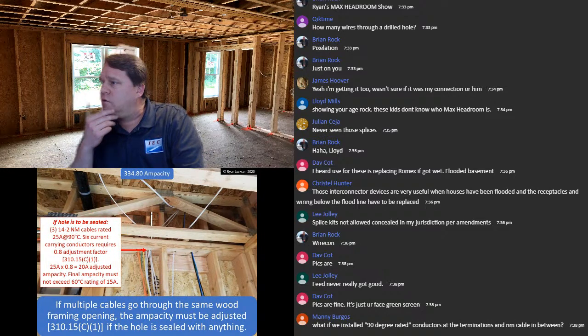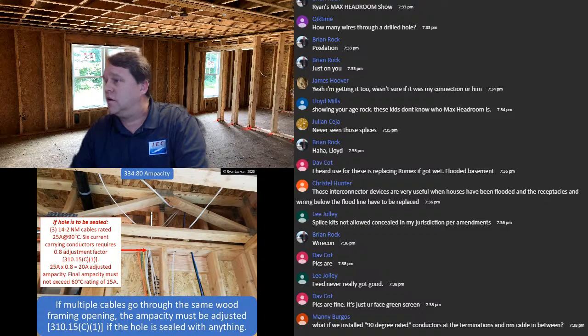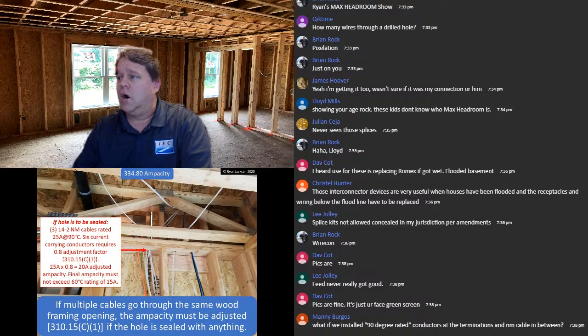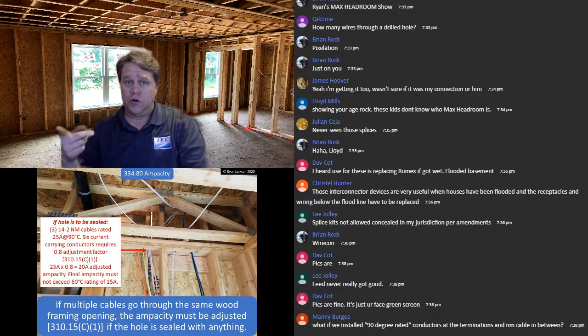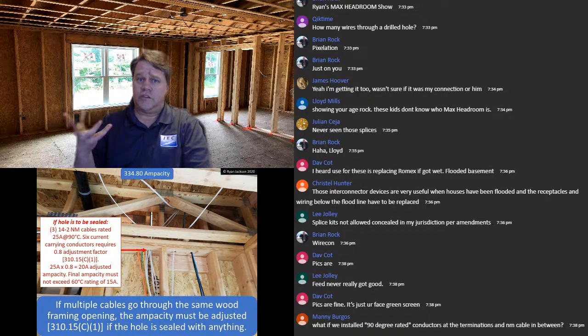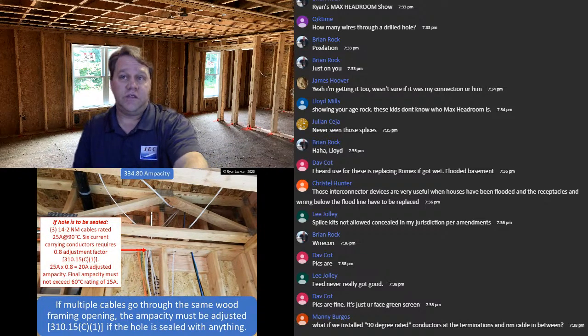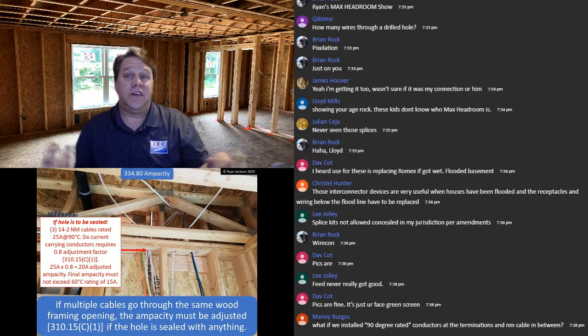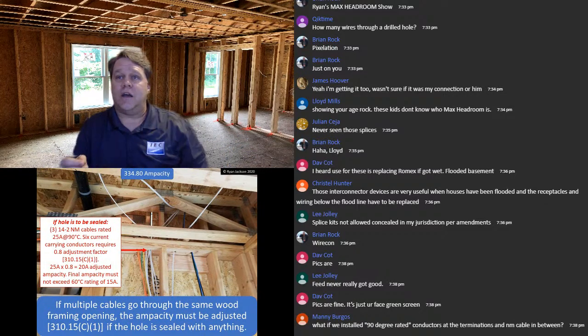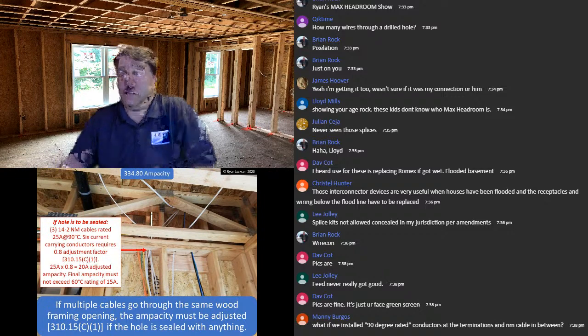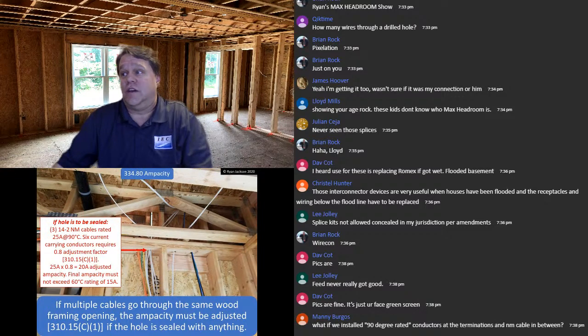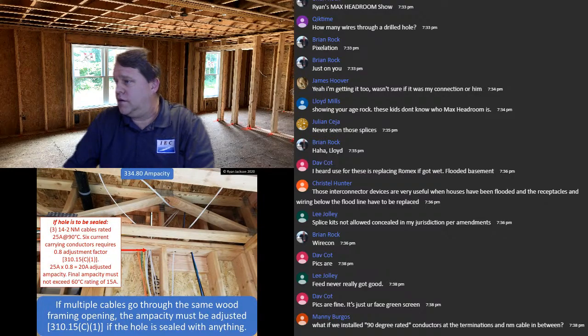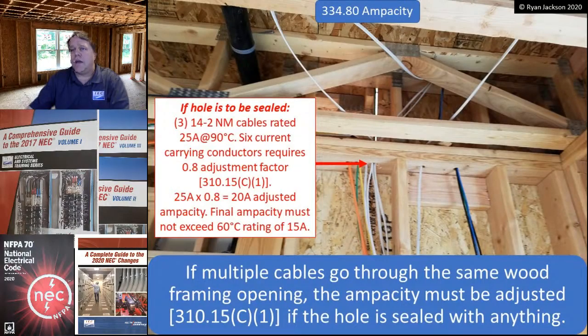What if we installed 90 degree conductors at the terminations and 60 degree NM cables in between? Yeah, you're fine, Manny. We treat the ends of the conductors different than the middle of the conductors. So for your luminaire, if your luminaire says you need 90 degree wires, splice on some 90 degree wires using one of these interconnector devices. I think you wanna go about 2 feet of cable. Push that thing up in the attic where you made the splice, good to go. It's a solution that otherwise doesn't really exist. All right, let's get back to this.